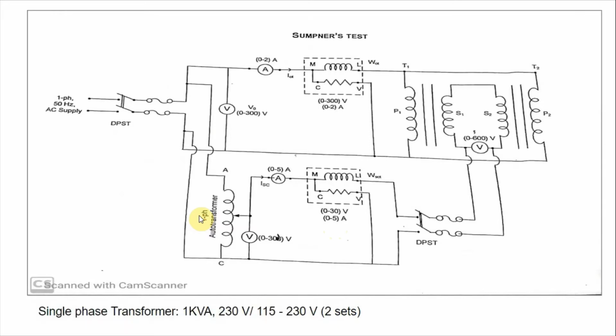Before explaining the circuit diagram, we'll look into the principle behind Sumpner's test. This test is also called the back-to-back test or regenerative test. Back-to-back test because one transformer acts as a load on the other transformer. And regenerative test because the output is not wasted here. This test is used to determine the efficiency, voltage regulation and temperature rise under loaded condition. The OCSC test can give us parameters of the equivalent circuit of the transformer, but it cannot help us in finding the heating information.